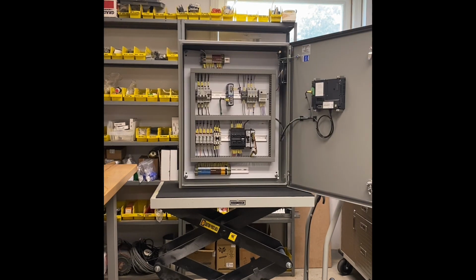This is the internal of the panel. Another slight oddity for one of my builds is to have a terminal strip located both top and bottom. The reason this job was done this way was because the original installation was done in such a manner that the wires crisscrossed the panel in a very haphazard, unprofessional manner. So I decided to add the terminal strip at the top so when my customer connects all of the wires external to this panel, it will still be in a neat, professional manner for the end user.